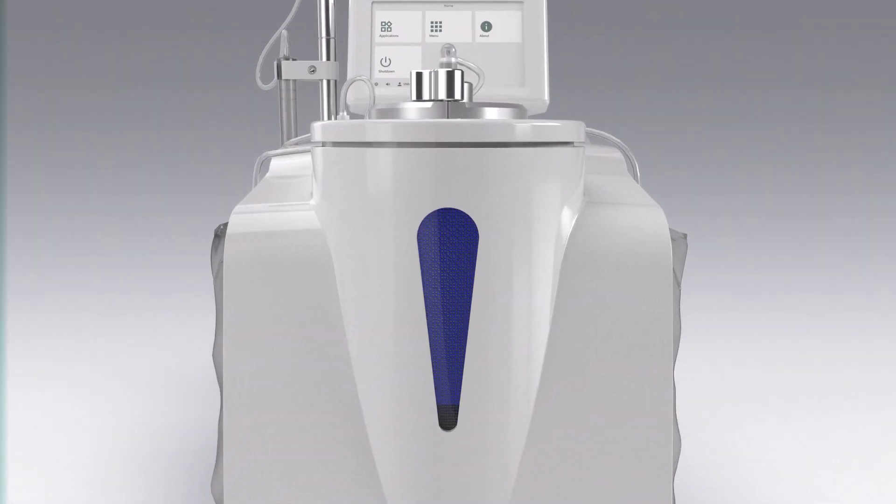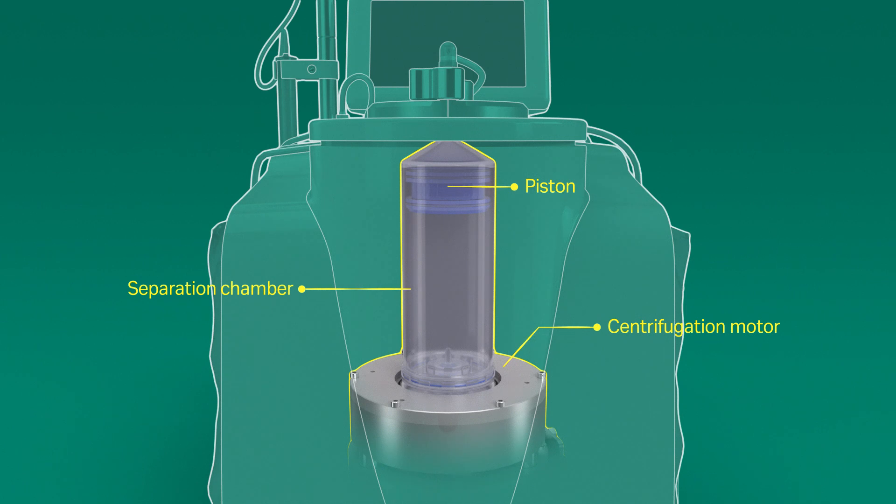The electric centrifugation motor and pneumatic circuitry drive the separation chamber piston to enable filling, centrifugation and extraction steps using the single-use kit's separation chamber.